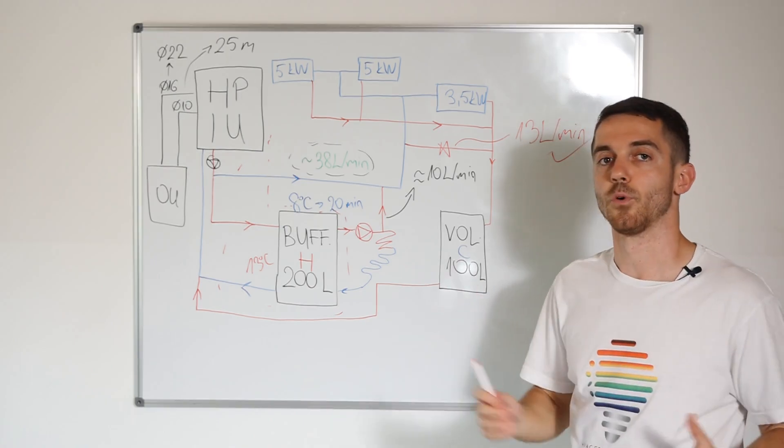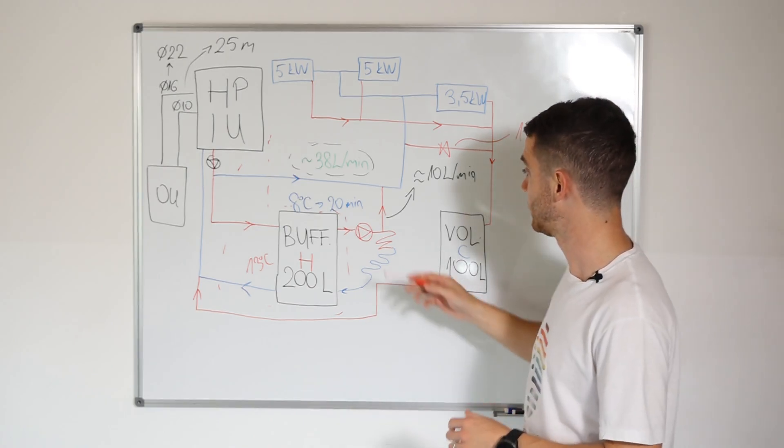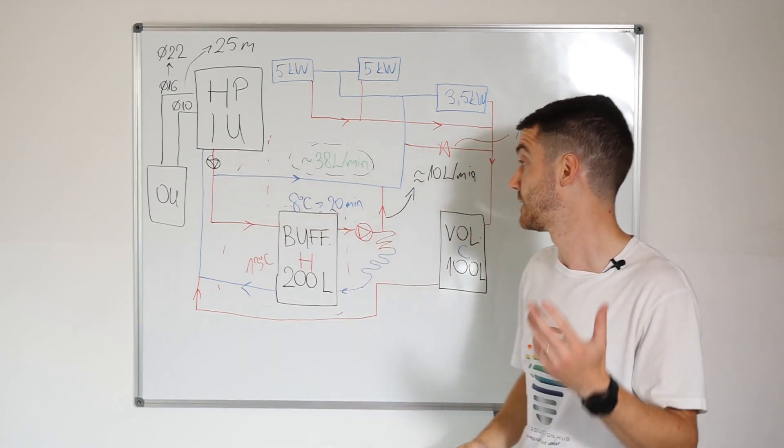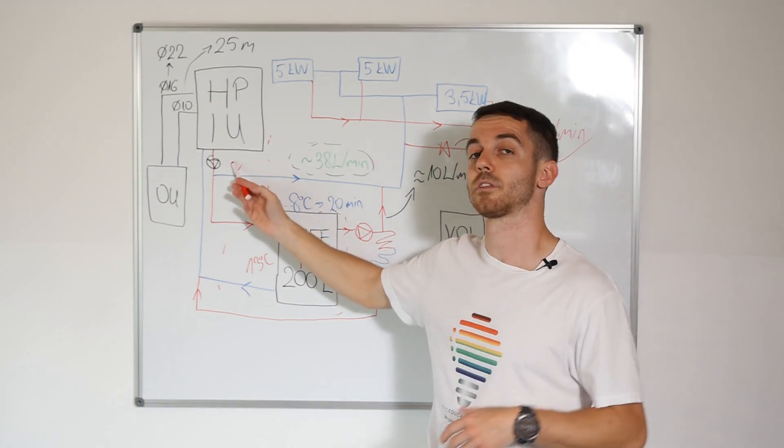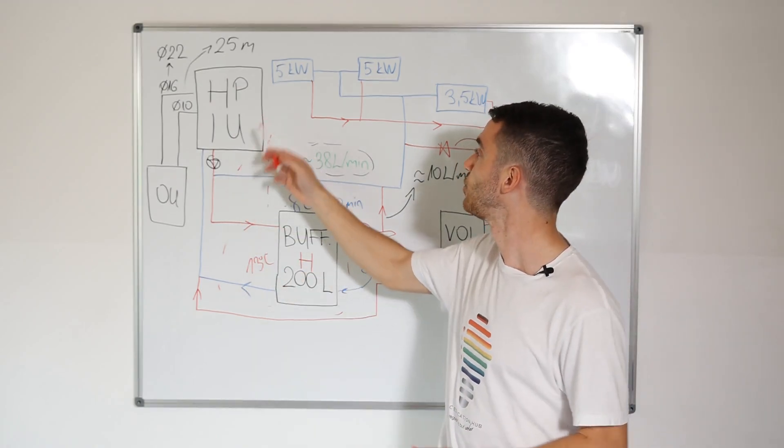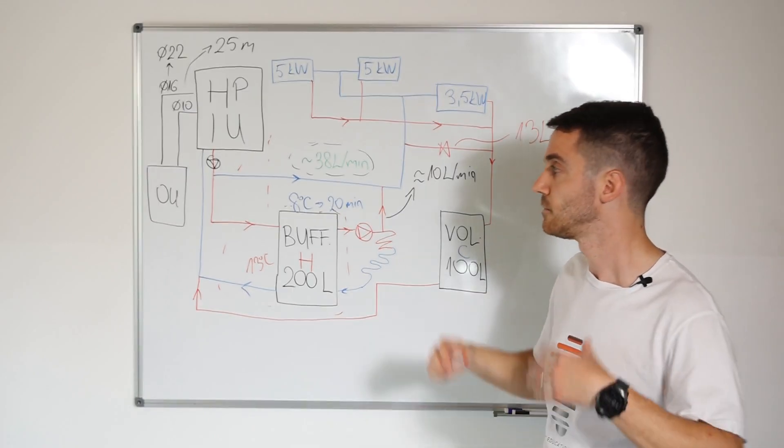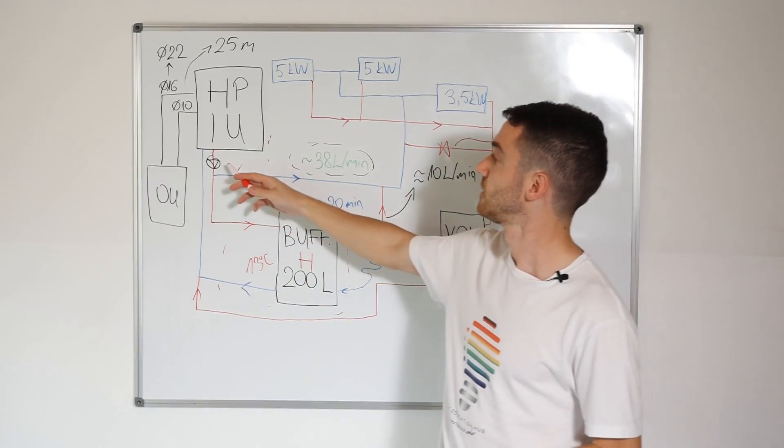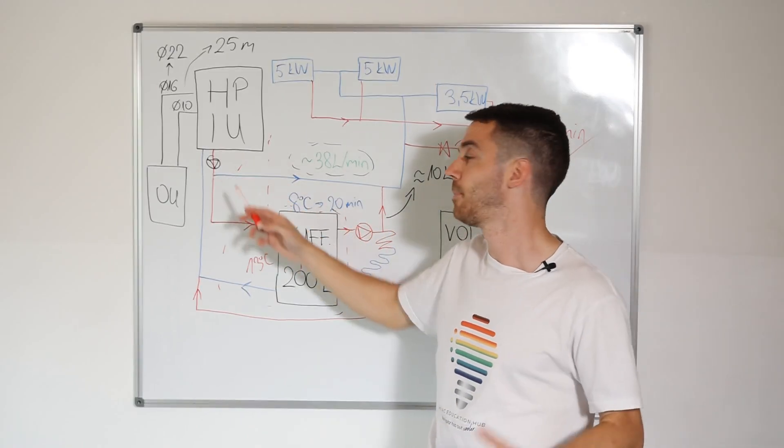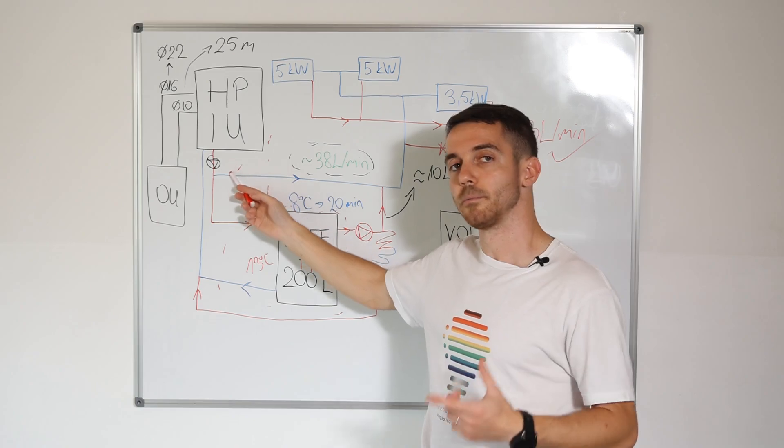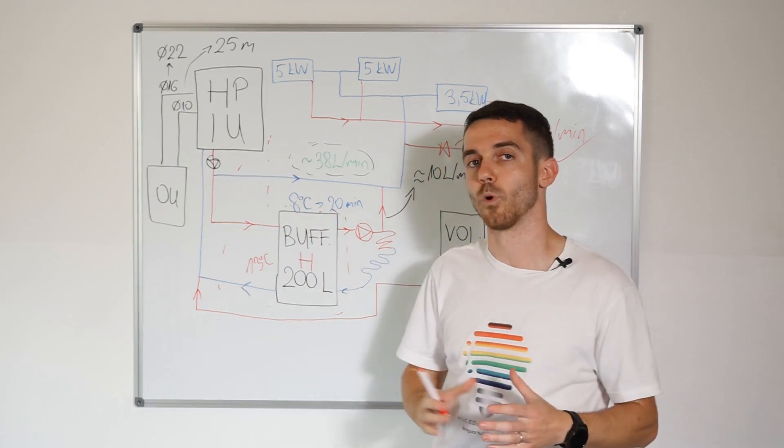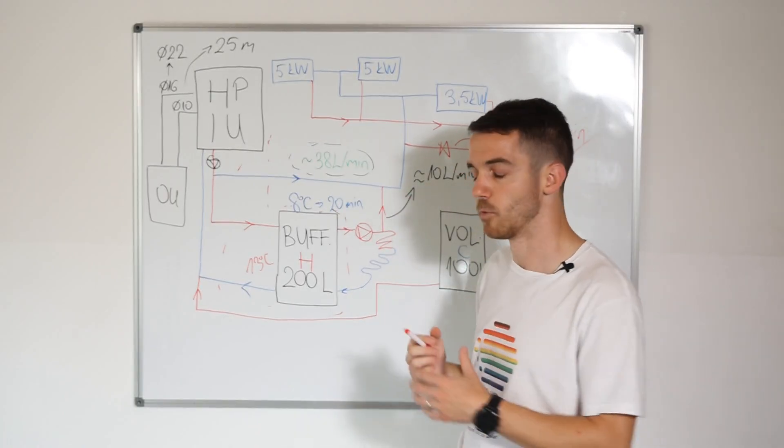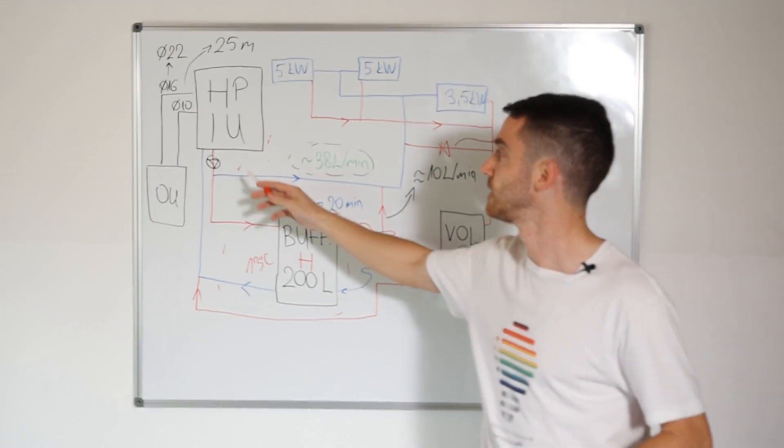Also, it was not clear for customer and for installer why this pump is working, so this Grundfos pump, and this pump is not working. They said that this pump is not strong enough to feed these fan coils. This is not true because this pump is stronger than this pump. But internal pump of heat pump needs to follow algorithm and needs to have minimum flow rate to have proper operation. This pump could work on minimum, much lower than this one.